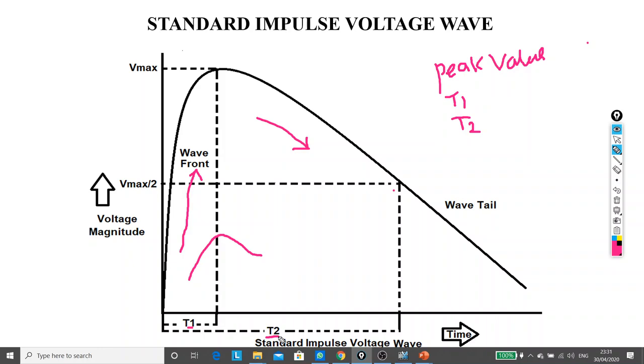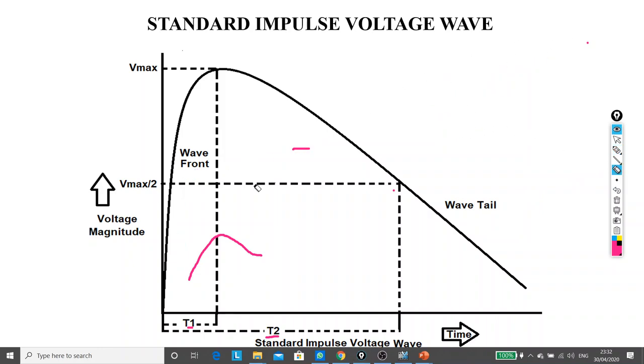The impulse voltage wave is a unidirectional wave — it can be a positive or a negative impulse voltage wave. This type of impulse voltage wave is required to be generated in the laboratory for testing high voltage insulators, because they are outdoor equipment and must bear the condition of a lightning stroke. Whenever a lightning stroke occurs, the nature of the voltage will be impulsive — either positive or negative — and the insulating devices must withstand it. So we need impulse voltage generators in the laboratory, and we will discuss the circuits used to generate the impulse voltage wave.